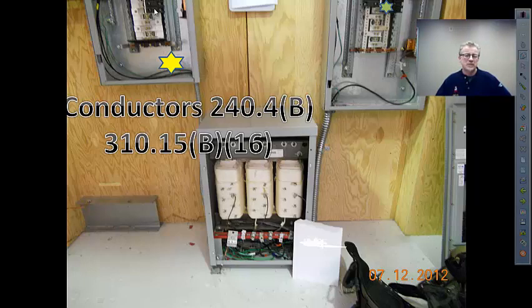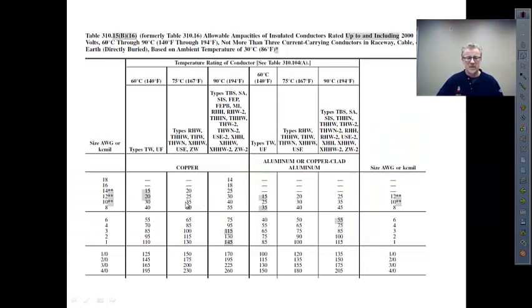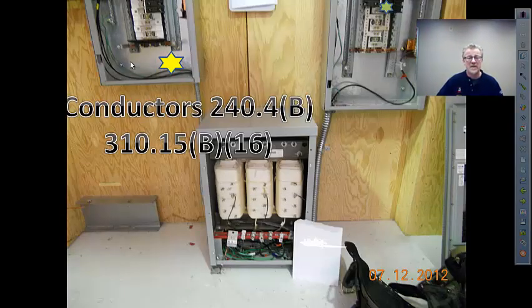Now, a 50 amp breaker is less than 70. It would be legal, but it might give you nuisance tripping. So the general practice is size that breaker as large as allowed to avoid nuisance tripping and having angry customers. Then we're going to size the conductors in accordance with 310.15(B)(16), the ampacity tables. And we chose that conductor, 65 amp wire, number 6. That's our primary.